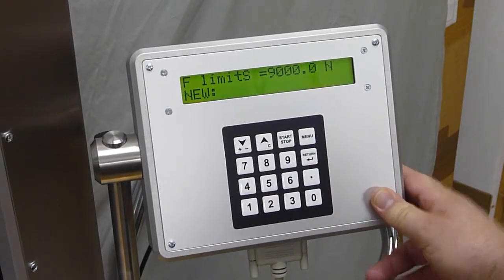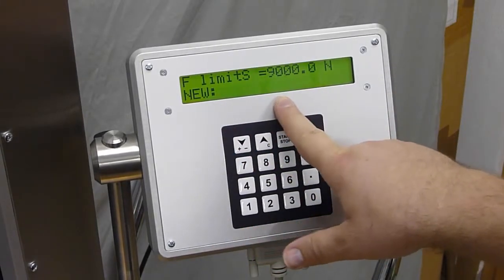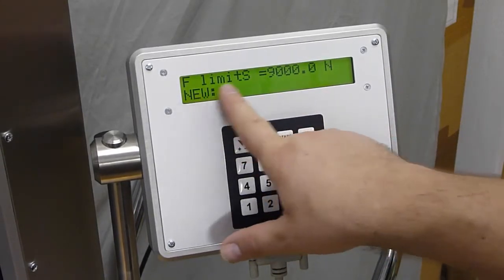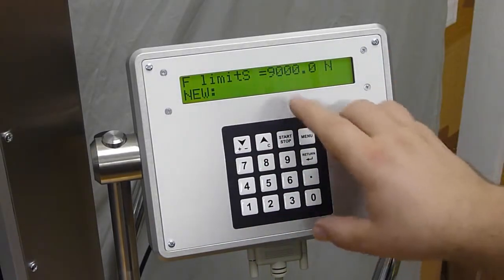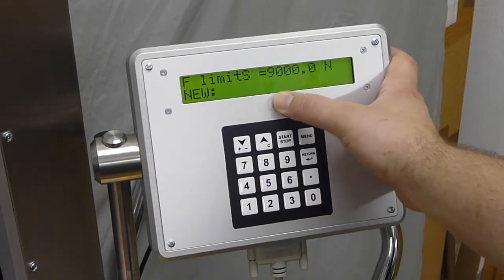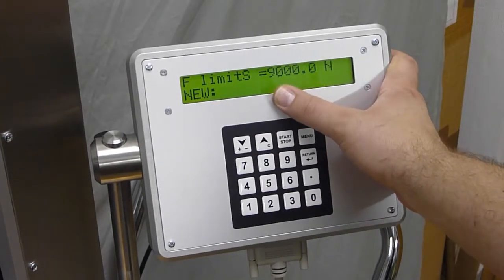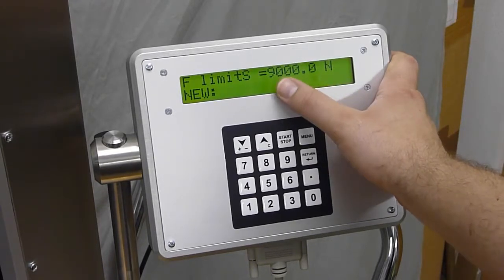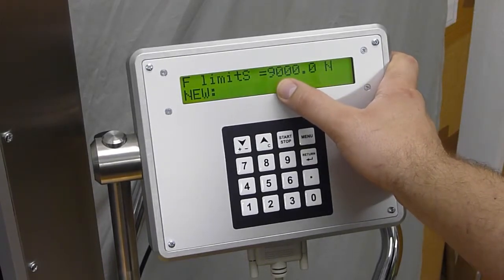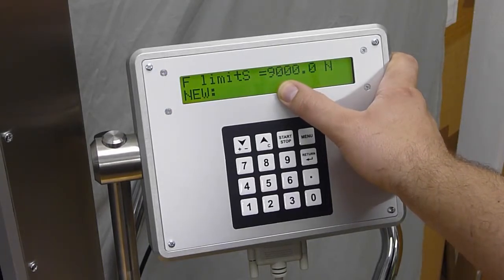F limit S. This is protection for sample, software protection. This means when during test the machine reaches 9000N it will break the test. The test will be stopped and the sample will be protected.